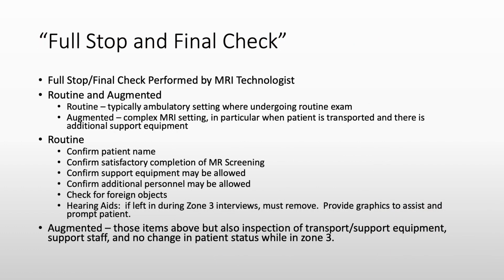A new recommendation in the 2019 MRI safety document was to conduct a full stop and final check. The 2024 ACR MRI Safety Manual devotes an entire chapter to this concept and provides further detailed guidance. There is a tiered approach to this full stop and final check. If you are in a routine setting, such as ambulatory and routine exams, this will be a fairly simple check. The MRI technologist confirms the patient name and completion of the screening form. They also confirm that support equipment has been screened and may be allowed, and any individuals that will be present with the patient are screened and given safety instruction.